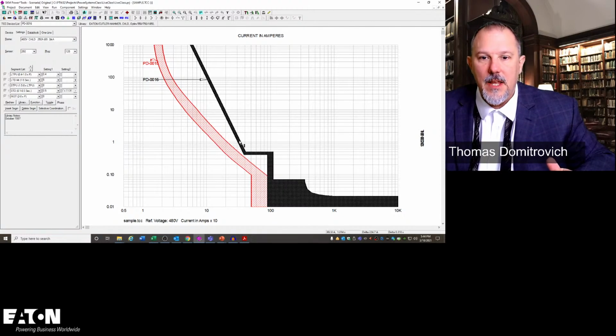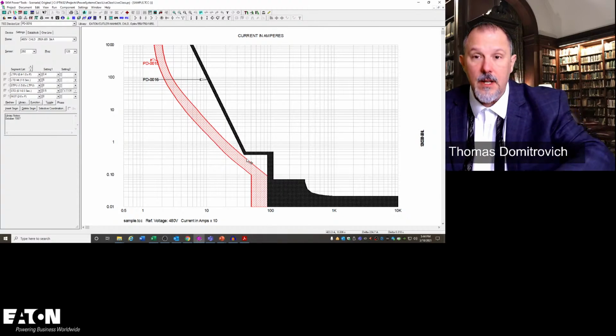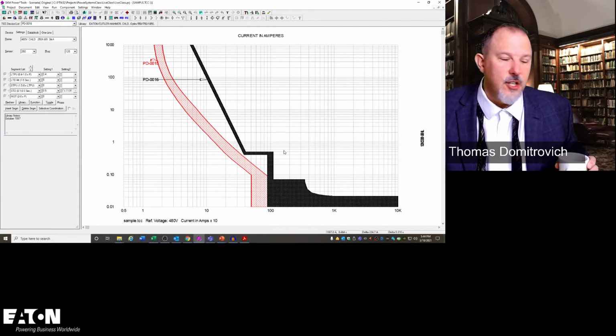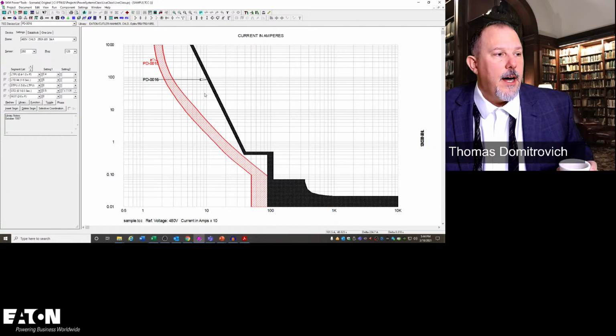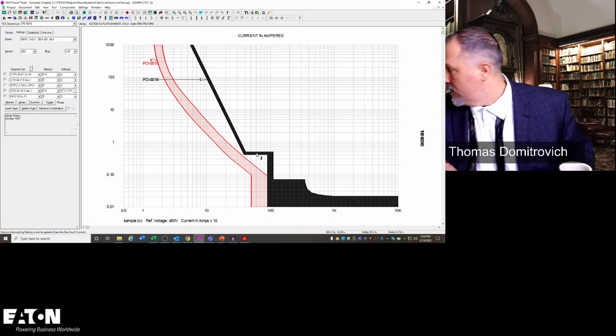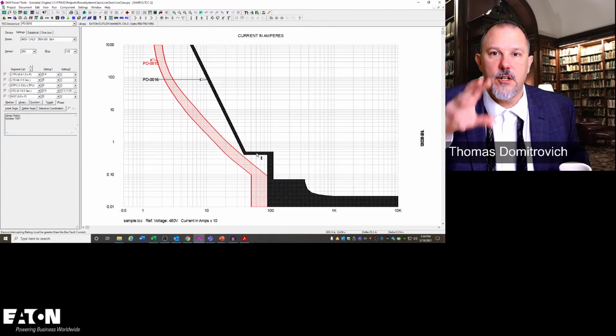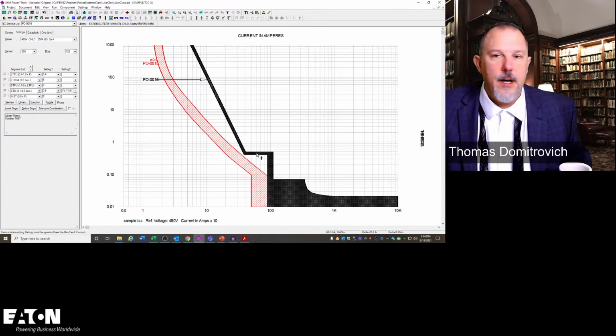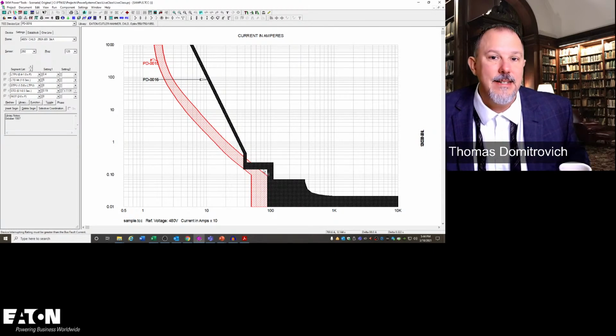So now in the overload region, which is these lower currents, in the long time, and this is what we call the short time delay, I can lower the short time delay. I can increase the short time delay. And you know what these are? These are dials on the circuit breaker. Okay, they're little dials on the circuit breaker. When I rotate a dial, I could be changing the time, which is a delay, or I can be changing a pickup, which is a current value.